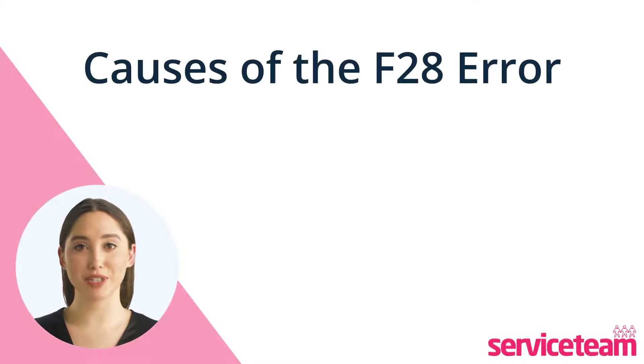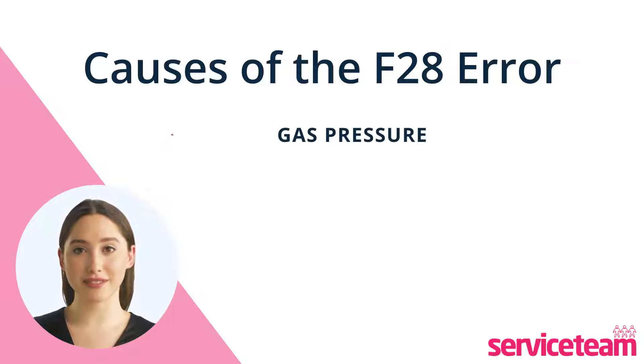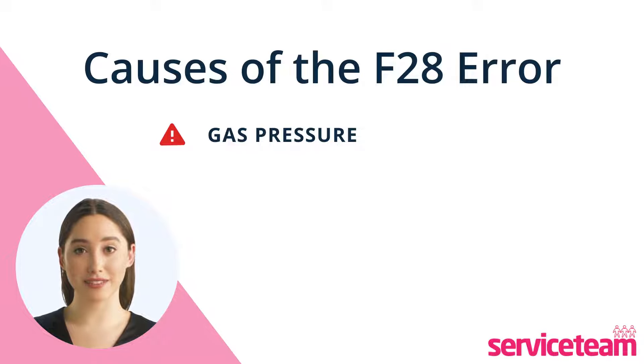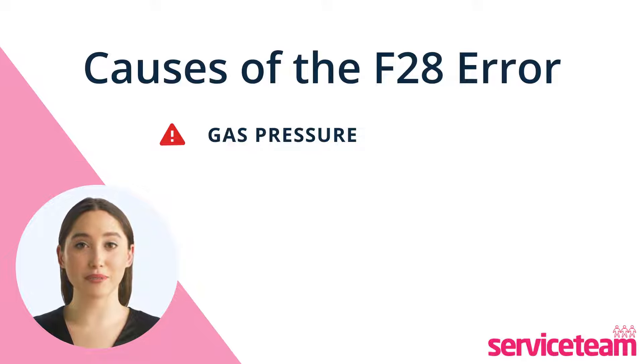Let's understand what causes the F28 error. The first cause is the gas pressure. Boilers, both new and old, can face issues like insufficient gas pressure. If your new boiler is more powerful and not working, the problem might be with the gas supply.